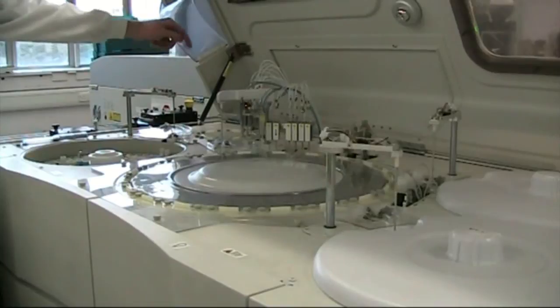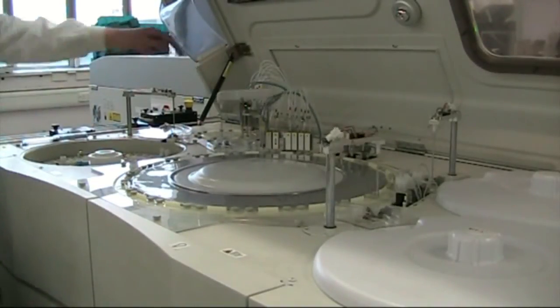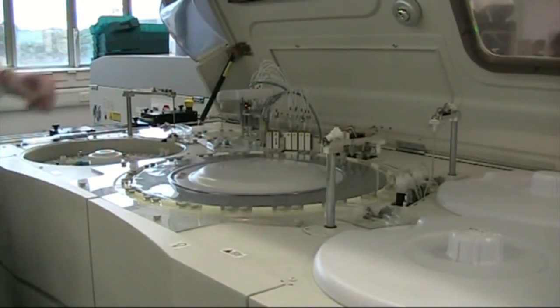And then it takes separate aliquots from the dilution turntable and puts those into a sample turntable there. You can see the probe is moving that sample to the sample turntable.